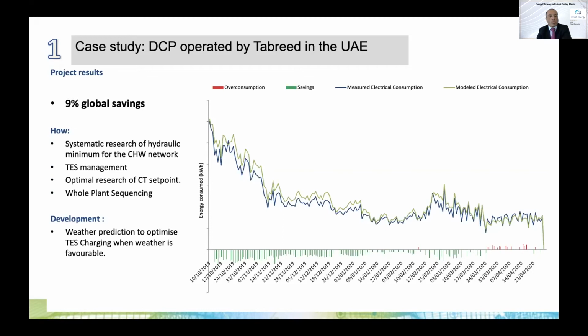So this is what I was mentioning earlier, minimizing the secondary pump speed as much as possible, implementing TES tank management, and the whole plant sequencing. Something that I'd like to point out, because I noticed there was a question with regards to smart solution and automation: while the system was on for a duration of 3 months, there was no operator intervention required. The operators were supervising and ensuring that nothing was getting outside of what was contractually allowable. But the system managed to sequence and run the plant automatically for 3 months, while generating 9% savings compared to standard operating practices.